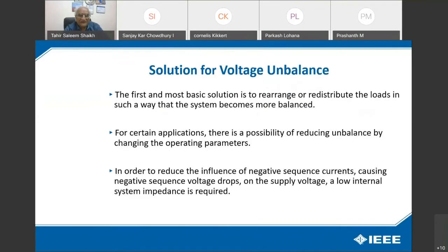The first and most basic solution is to rearrange and redistribute the loads in such a way that the system becomes more balanced. For certain applications, there is a possibility of reducing unbalance by changing the operation parameters. This you can do yourself. In order to reduce the influence of the negative sequence currents causing negative sequence voltage on the supply voltage, low internal system impedance is required.